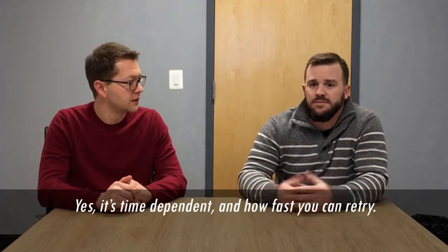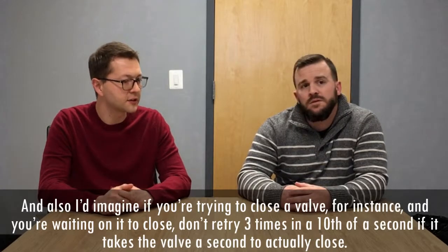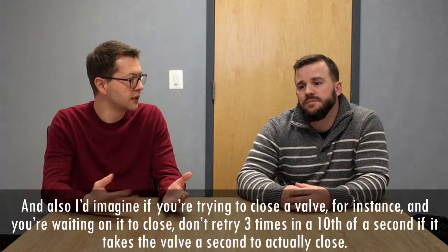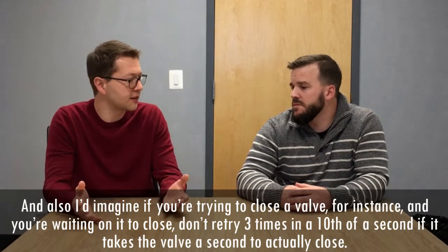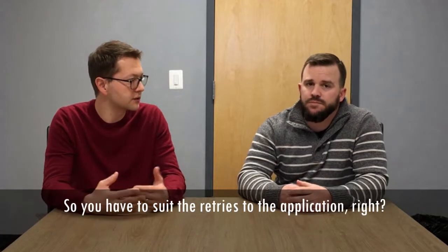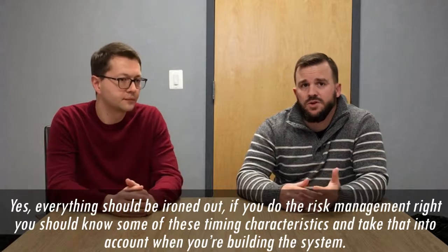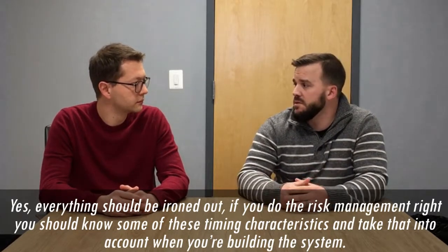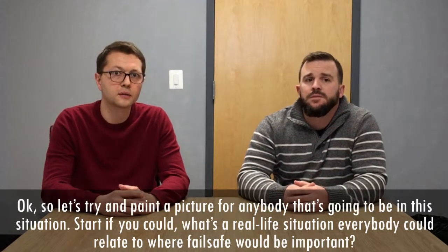It's time dependent and how fast you can retry. Okay. And also I'd imagine too, if you're trying to close a valve, for instance, and you're waiting on it to close, don't retry 3 times in 1/10 of a second if it takes the valve a second to actually close. Yeah. So you have to kind of suit the retries to the application, right? And everything should be ironed out if you do the risk management right. You should know some of these timing characteristics and take that into account when you're building the system.